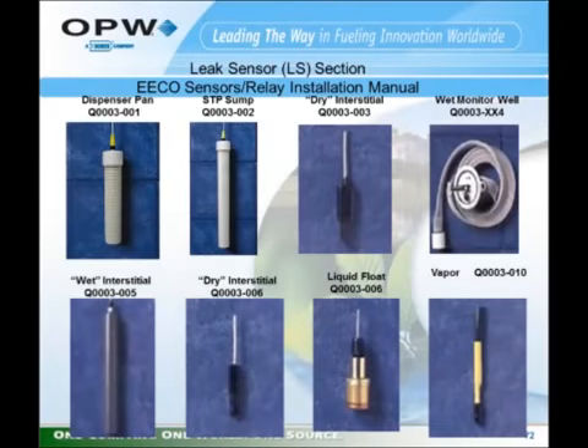Leak sensors. The EECO tank gauges support multiple types of leak sensors, different models, but all preceded with a Q0003 as part of the model number. This is the current family of sensors. Any existing sensors in the field whose model number starts with Q0001 or Q0002 are not compatible with the current EECO sensor interfaces being supplied by OPW. Those sensors will not work on current equipment, and there are no replacements available for those old sensors.